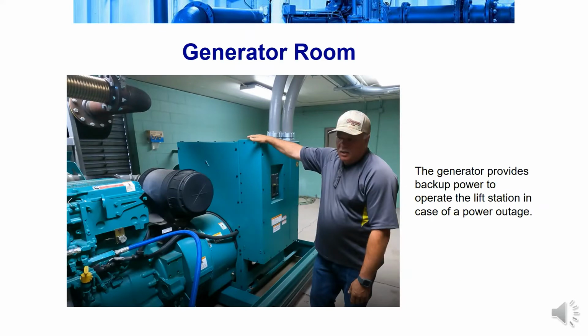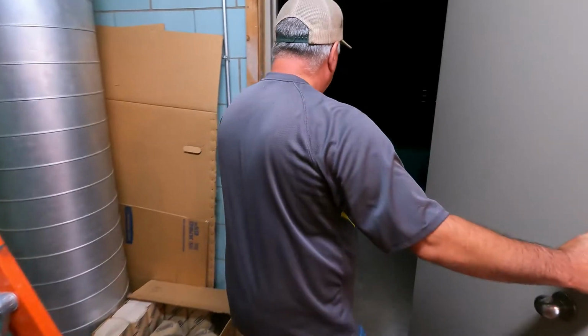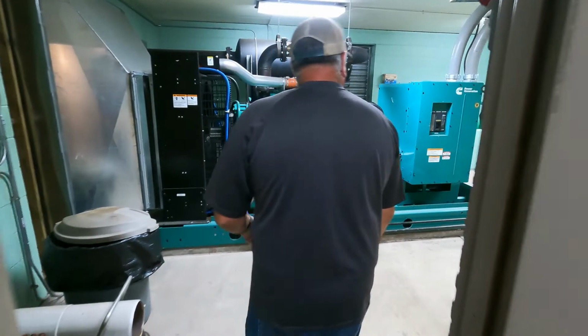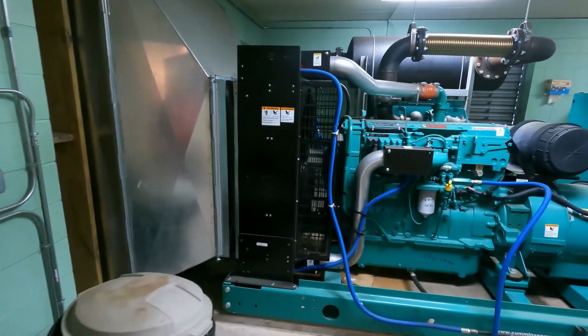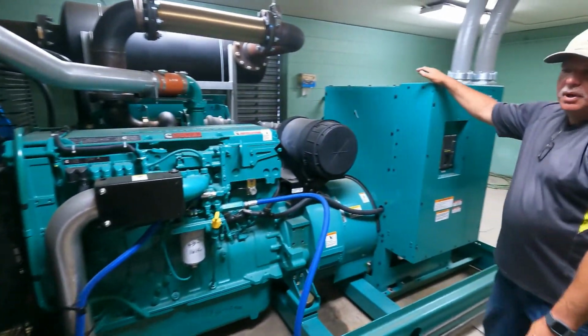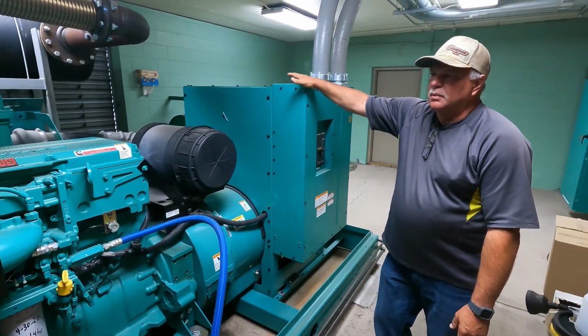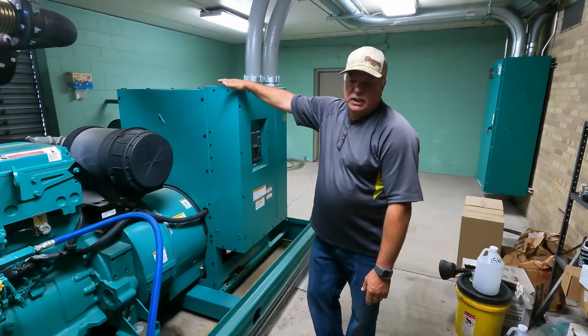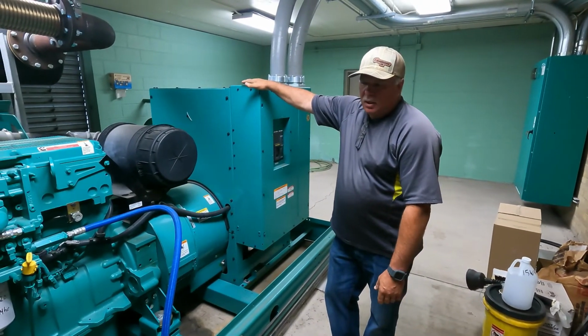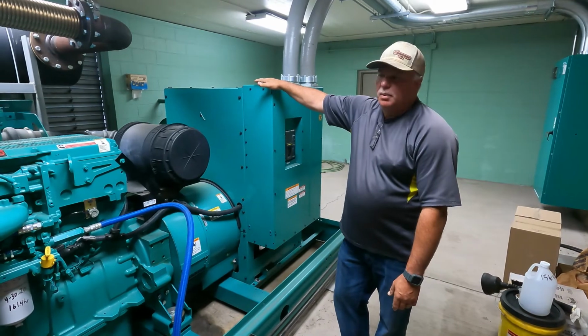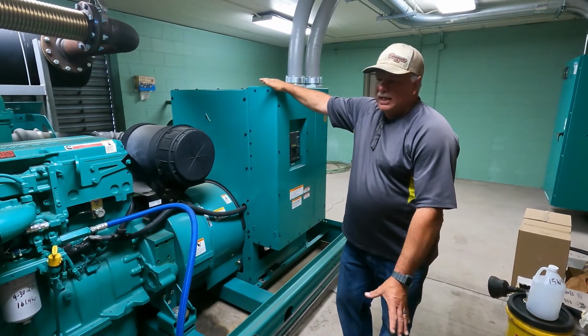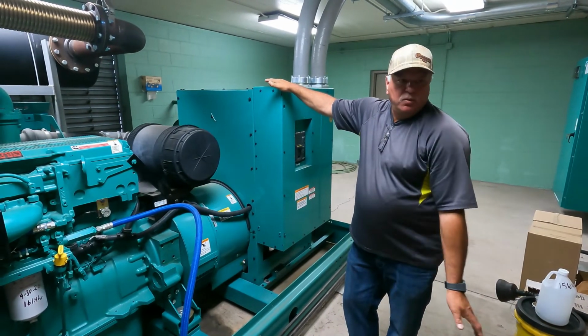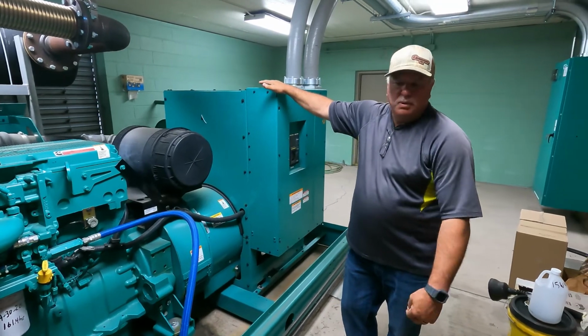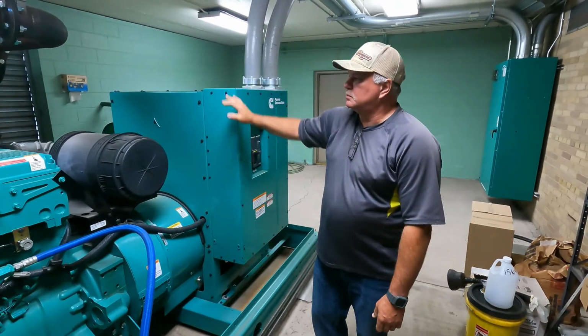Moving on now to the backup generator room for the Portage lift station. So in the event of a power fail, we can still pump the water out to the main treatment plant. Each lift station and the main plant all have their own auxiliary power sources. This is sized such that it will run all 4 pumps and all the equipment that we need to run to effectively pump the wastewater out to the plant.